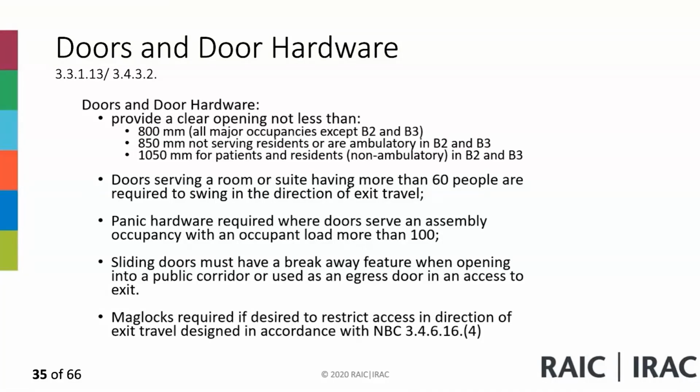Mag locks or magnetic locks are required if desired to restrict access in the direction of exit travel. They need to be designed in accordance with the provisions in 3.4.6.16(4). The code does not require mag locks, but if you're going to use them, there are restrictions on using magnetic locks for keeping a door open or for controlling security access to certain areas.